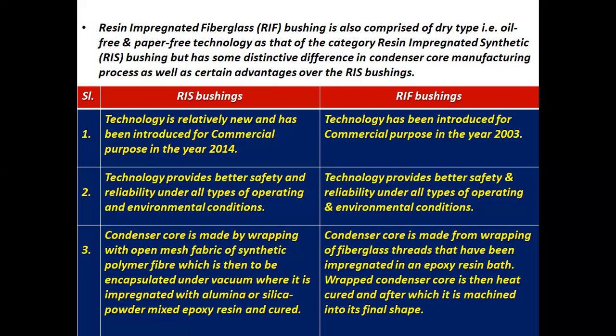Number 3, the condenser core is made by wrapping open mesh fabric of synthetic polymer fiber, which is then encapsulated under vacuum, where it is impregnated with alumina or silica powder mixed epoxy resin and cured. But for RIF bushings, the condenser core is made from wrapping of fiberglass thread that has been impregnated in an epoxy resin bath.